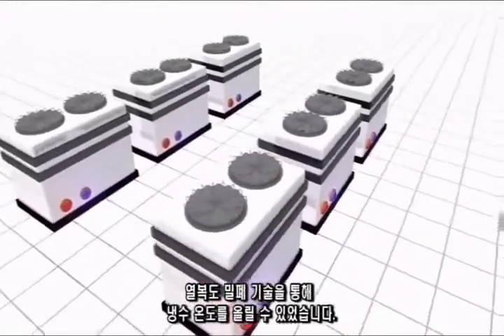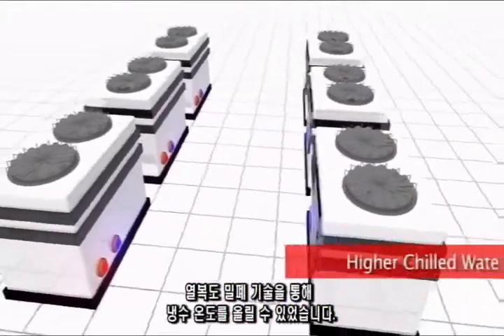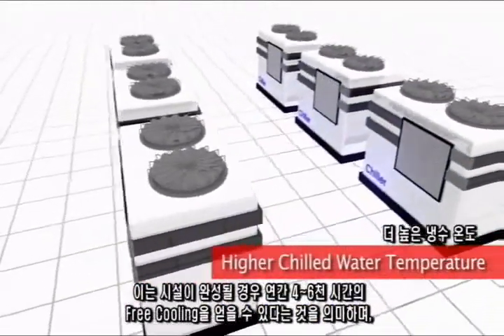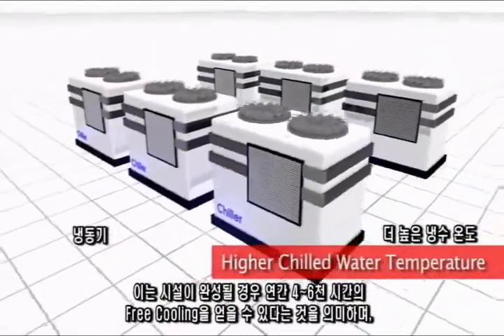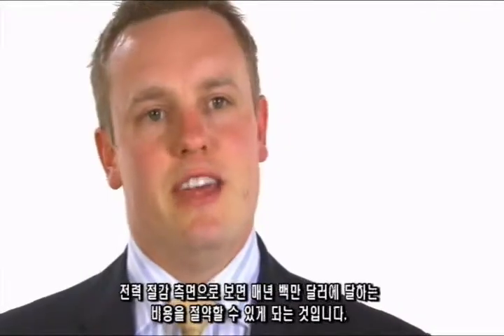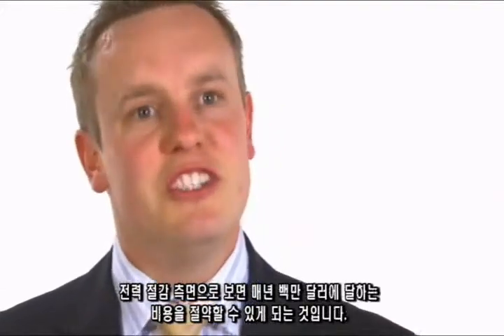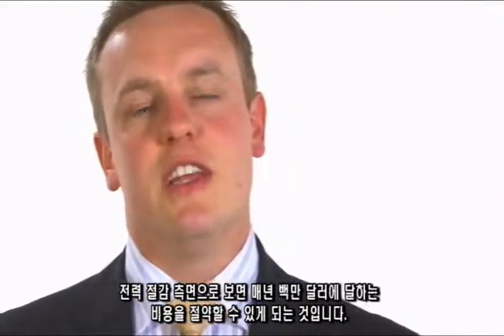With the hot aisle containment, we were able to raise our chilled water temperature. Now, this for us meant that we could get between 4,000 to 6,000 hours a year of free cooling, and that directly translates into about $1 million a year in terms of power saving once the facility is full.